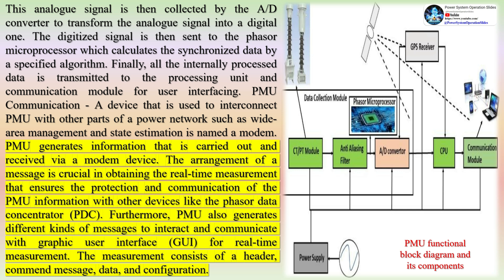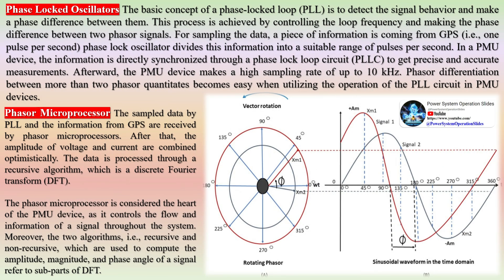The internal structure of the PMU device consists of many important electrical and electronic components that are critical for the accuracy and delivery of PMU information. These components consist of GPS, modem, AD converter, anti-aliasing filters, phasor microprocessor, and phase-lock loop oscillator. The analog signal is collected by the A-D converter to transform it into a digital signal. The digitized signal is then sent to the phasor microprocessor, which calculates the synchronized data by a specified algorithm. Finally, all the internally processed data is transmitted to the processing unit and communication module for user interfacing.